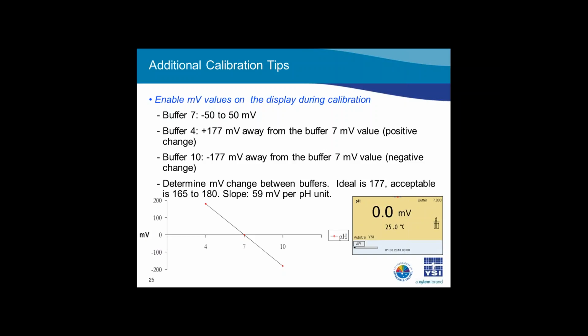Evaluating the millivolt values will also tell us how good our calibration is or if we're nearing the outer edge of the acceptable limits. This can help us plan for future maintenance or replacement requirements. The acceptable values for the millivolt signal in buffer 7 is between -50 and +50. This is a general rule for all pH electrodes.